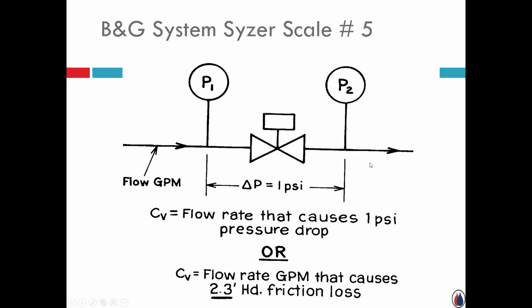Yes, sir. Well, it would actually be lower, right? Meaning my inlet pressure, and it's not like 1 jumping up to 2. It's saying, here's my inlet pressure, and I'm going to be 1 pound lower. I've had a pressure drop of 1 PSI, and they want to measure what was the flow rate through the valve to cause that 1 pound pressure drop. Yes, yeah, if you want to call it high and low, inlet high, outlet low.